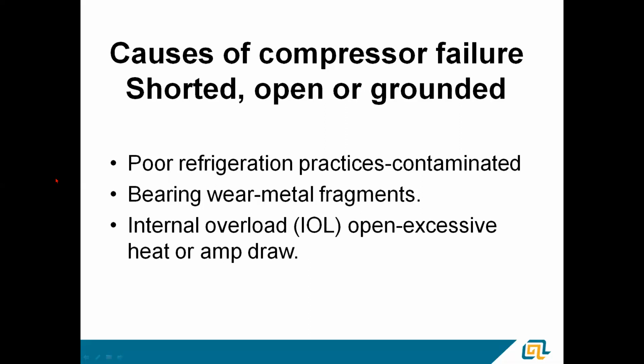Internal overload opens, either excessive heat or amp draw. Either one will do it. Like any other Klixon, they'll cycle, maybe a couple hundred times, but eventually they just get tired of doing it. And they're going to fail in the open position, and then you'll have an open winding in the compressor.